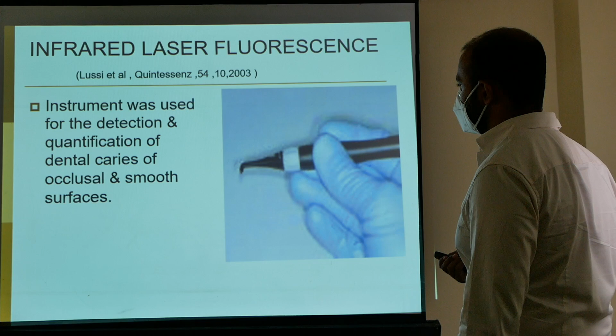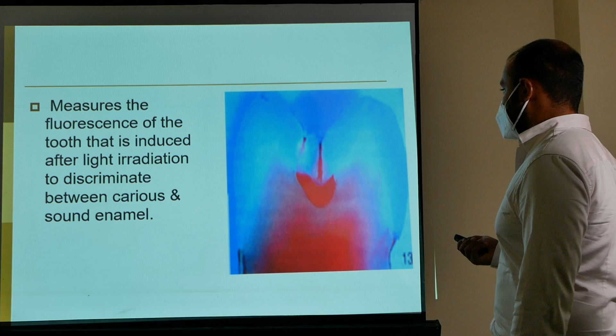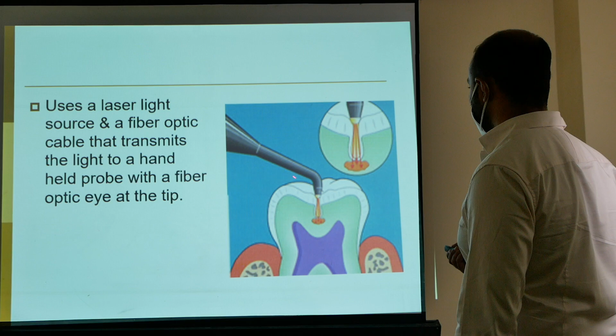Infrared laser fluorescence instrument was used for the detection and quantification of dental caries of occlusal and smooth surfaces. It measures the fluorescence of the tooth that is induced after light irradiation to discriminate between carious and sound enamel. It uses a laser light source and a fiber optic cable that transmits the light to a handheld probe. This is a handheld probe with a fiber optic eye at the tip.